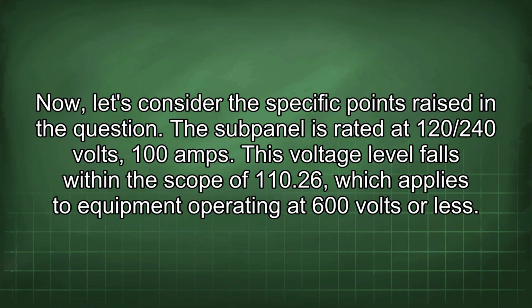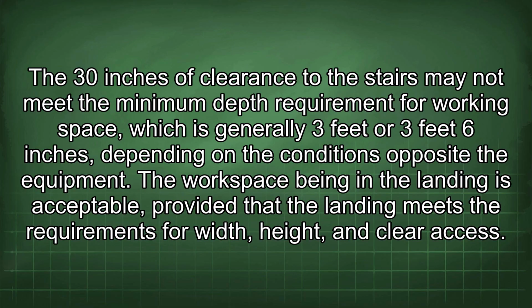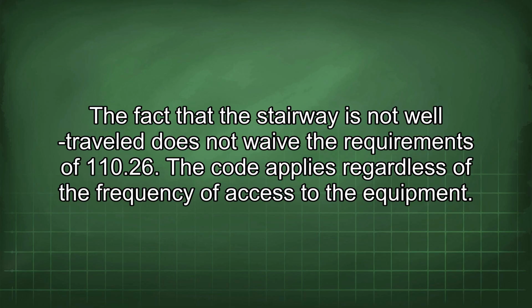Now, let's consider the specific points raised in the question. The subpanel is rated at 120/240 volts, 100 amps. This voltage level falls within the scope of 110.26, which applies to equipment operating at 600 volts or less. The 30 inches of clearance to the stairs may not meet the minimum depth requirement for working space, which is generally 3 feet or 3 feet 6 inches, depending on the conditions opposite the equipment. The workspace being in the landing is acceptable, provided that the landing meets the requirements for width, height, and clear access. The fact that the stairway is not well traveled does not waive the requirement of 110.26. The code applies regardless of the frequency of access to the equipment.